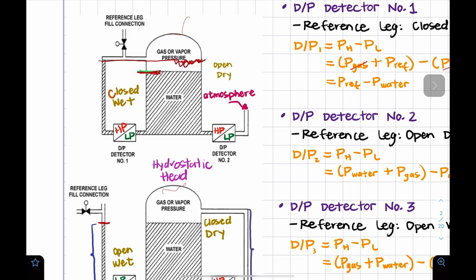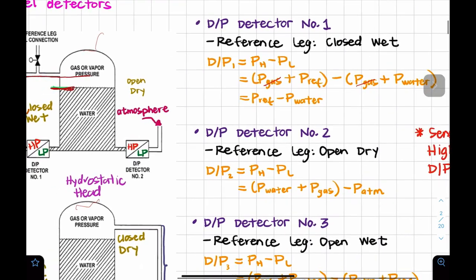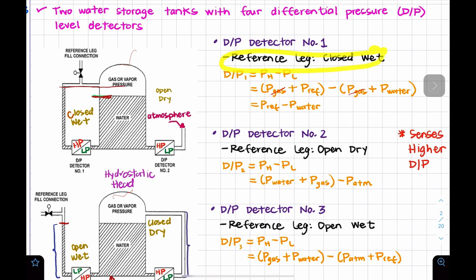When the liquid level in the tank goes down, the pressure applied to the low pressure side decreases, and the differential pressure increases. As a result, differential pressure and transmitter output are inversely proportional to the tank level. The formula for differential pressure is always: ΔP = P_high − P_low. For detector one, the high side is the reference leg, and the formula becomes: ΔP = (P_reference + P_gas) − (P_water + P_gas).